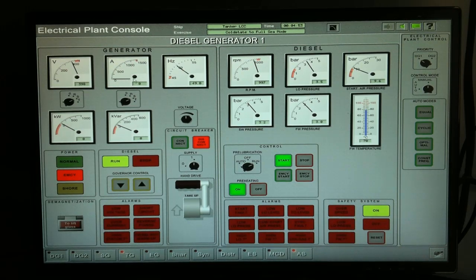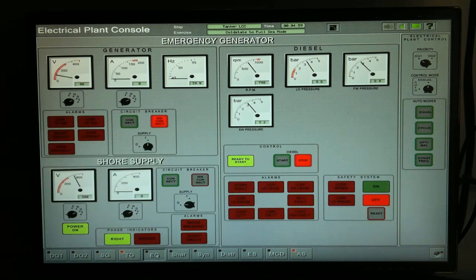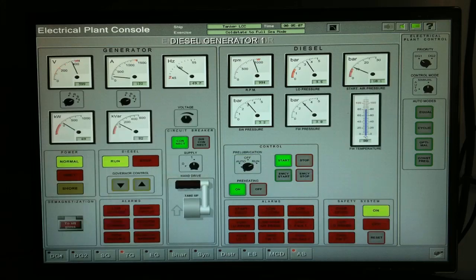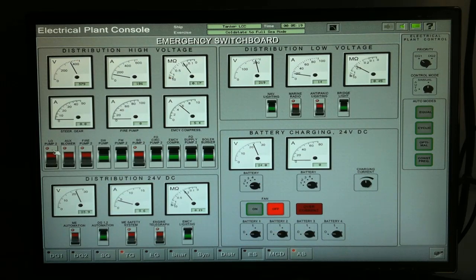Okay, we have now voltage and hertz. Connect. Okay, then check on your emergency. So, no more load on the emergency generator. The emergency generator will automatically stop. Okay, once you have the main generator running, set your pre-lube to auto, preheating to off. Once generator number 1 is running, proceed back to the ERS, open the remainder of the circuit breakers.